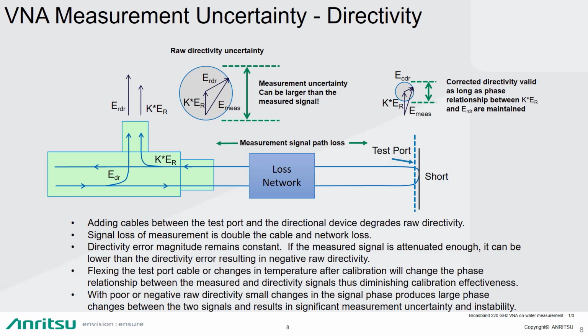So now any kind of flexing of the test port cable or changes in the temperature after the calibration will change the phase relationship between the measured and directivity signals, and thus you're going to start diminishing the effectiveness of your calibration corrections. And so when you have poor or negative raw directivity, these small changes in that signal phase can produce quite large phase changes between those two signals, and thus it results in a significant increase in measurement uncertainties and in instabilities.